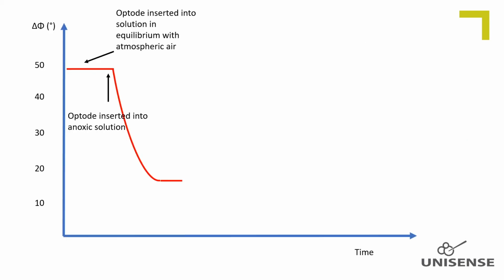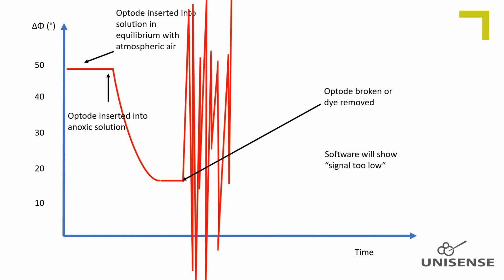I now turn to troubleshooting oxygen micro-optodes which do not exhibit normal performance. Naturally, small glass fiber optodes are fragile, and the tip might break if it hits something hard. A broken sensor will not get any fluorescent signal back from the fiber, and the optode meter software will indicate that with a signal too low prompt. The meter will still try to calculate the phase shift, but there is no real data input for the calculation, and the values will therefore be all over the place.